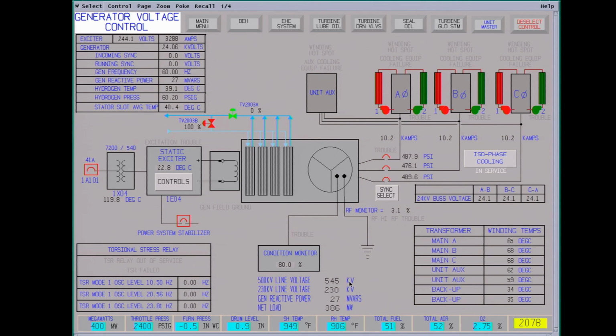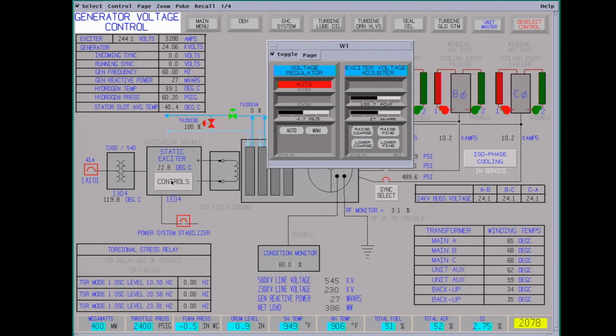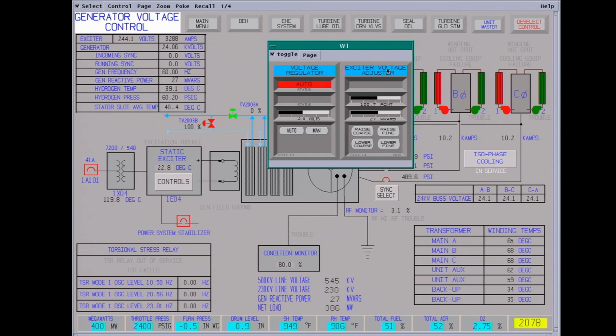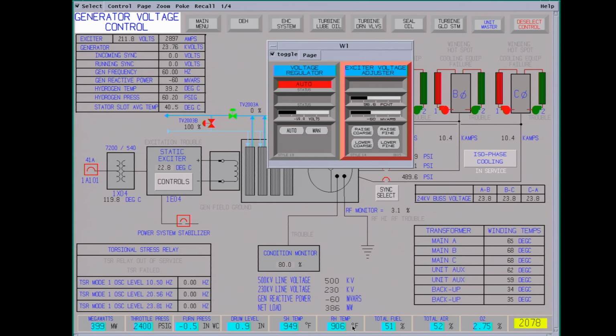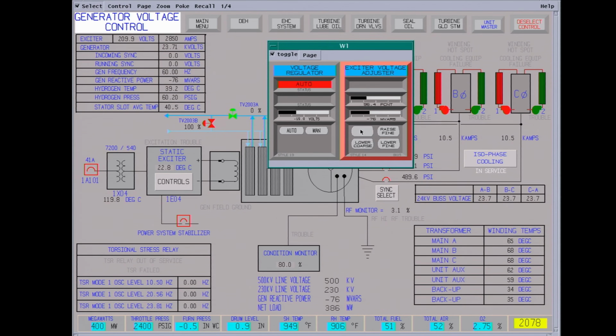Down here we have 545 kV. We've called the transmission operator, and they want us to try to buck it. So we're going to go to the exciter voltage adjuster, and we're going to start lowering. As you can see, the amps are dropping, volts are dropping. We're actually using it for a motor, trying to bring down the high voltage on the line. Overshot a little.